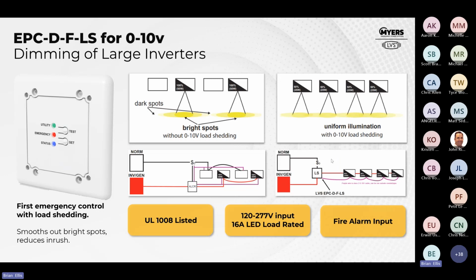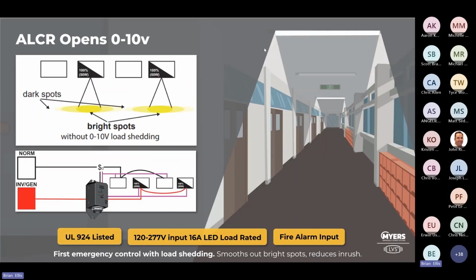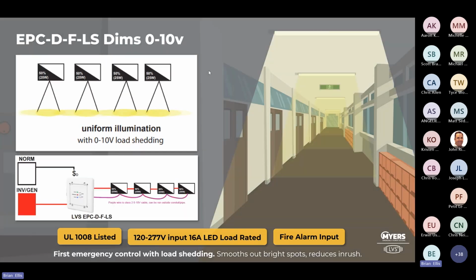Instead of having normal and emergency, we have one conduit with emergency, hot and neutral, and our 0 to 10. So we simplified the wiring, and we have even illumination, and we can reduce the size of our inverter and generator. So this, we think, is a really, really good solution. I have some examples later, which is going to probably put this into practical application for you. Here's kind of a visual of that, utilizing the ALCR, every other fixture at full light output and every fixture dark versus every fixture at a reduced light output.